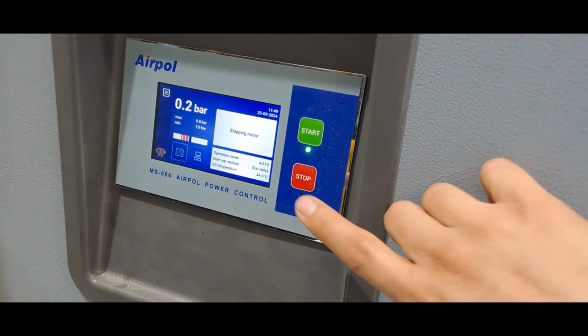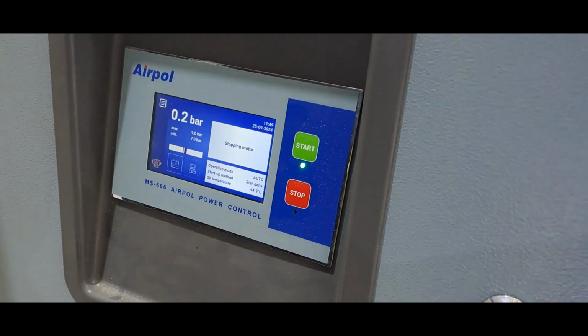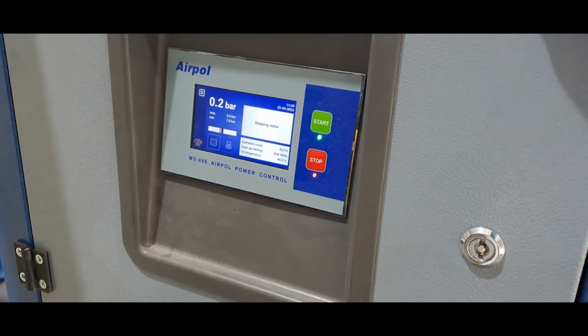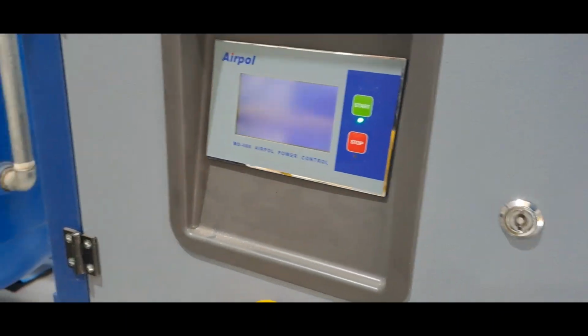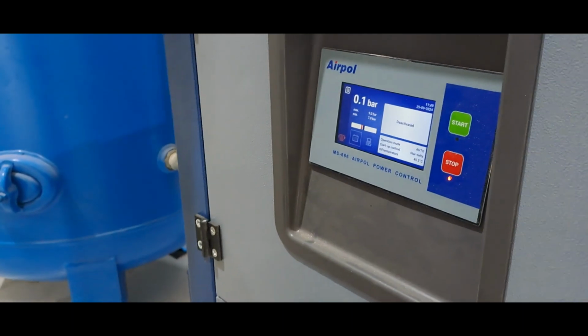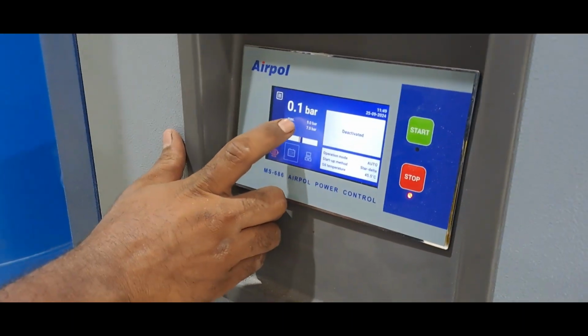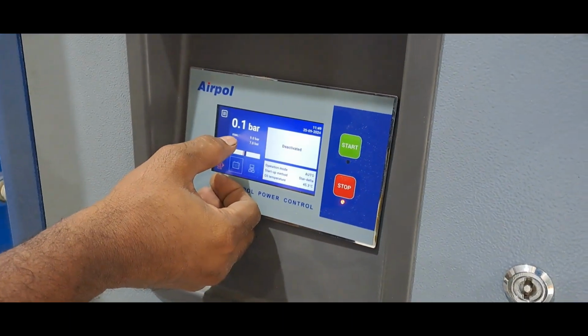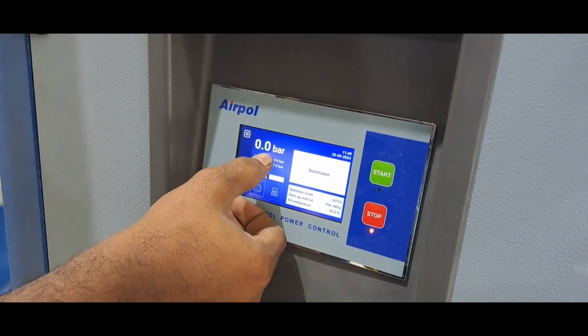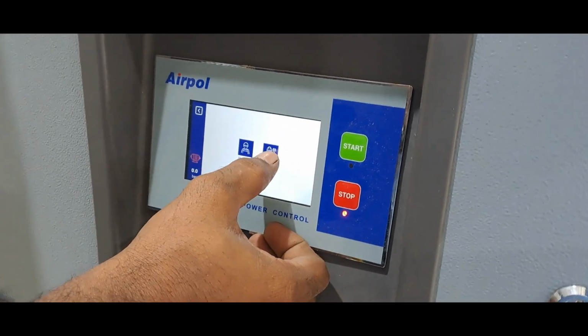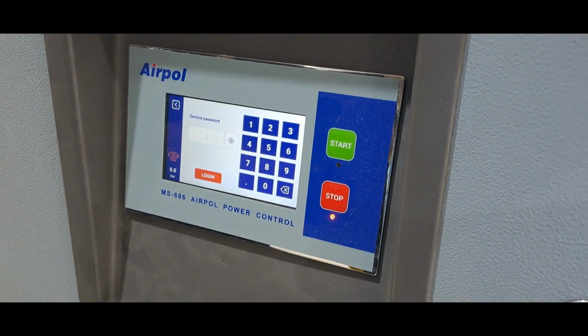So to stop, just press this stop button and the motor will stop. Now show us how to configure the set value, the set point, cut in and cut off. Here you are getting this option. Yeah, this is for configuration. Just press here. Service level. Password. Okay.